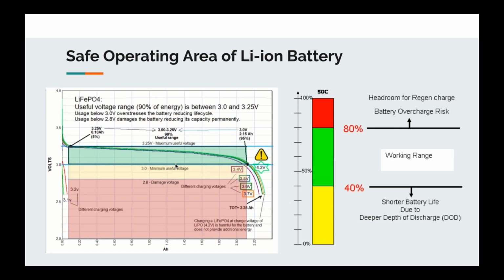Once the temperature reading goes red, we immediately cut off the load or cut off the charging input to the battery. We don't do anything further with the battery so it can cool down and come back into the safe operating area before we use it again. These three parameters—cell voltage, current, and temperature—ensure the battery operates within its safety area.